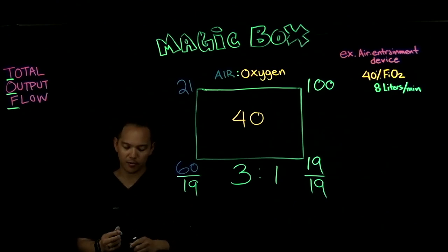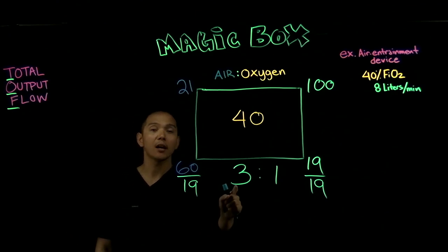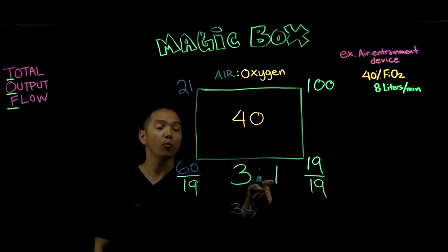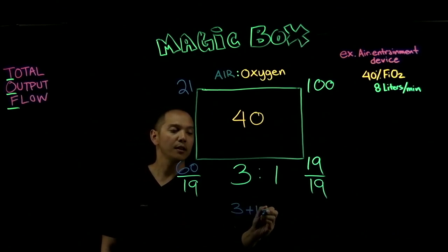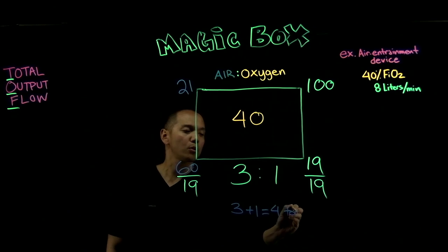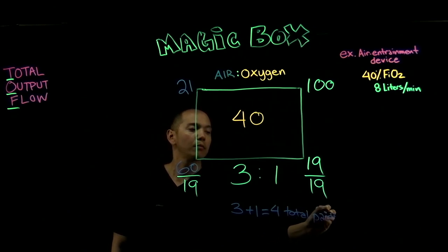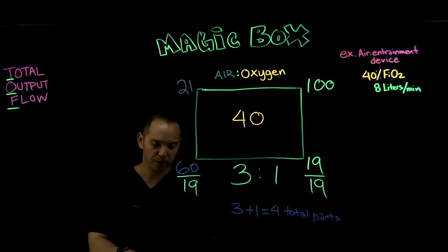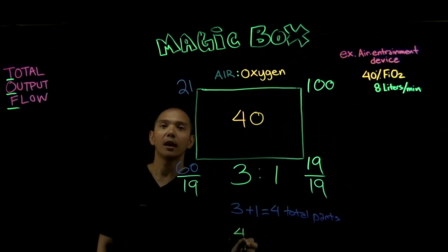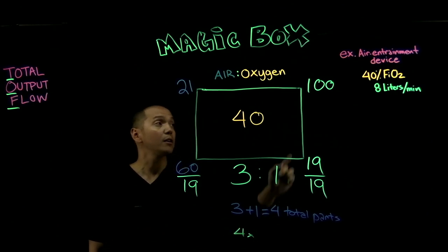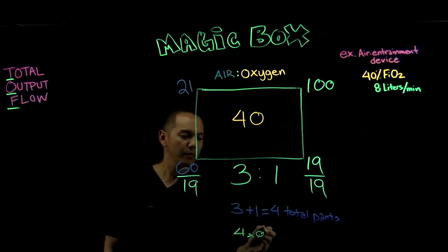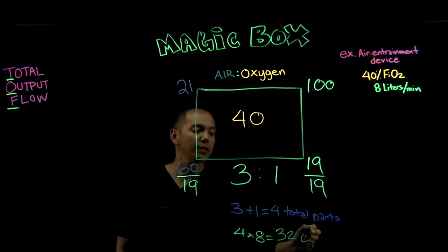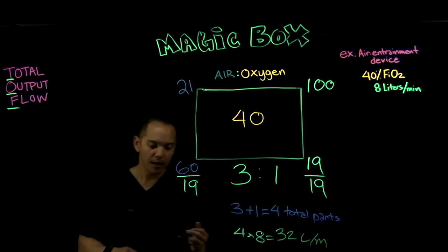To calculate total output flow, we take our three parts of room air and add it to our one part of oxygen, giving us four total parts. We then multiply those four total parts by our 8 liters per minute. Four times eight gives us 32 liters per minute.